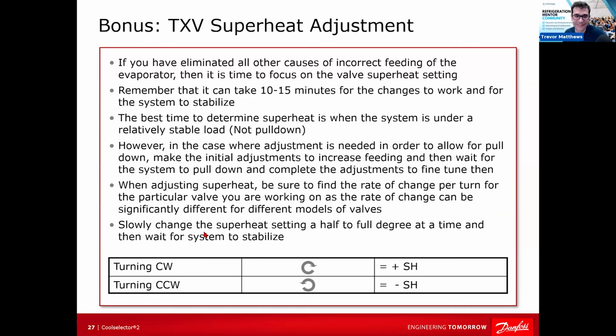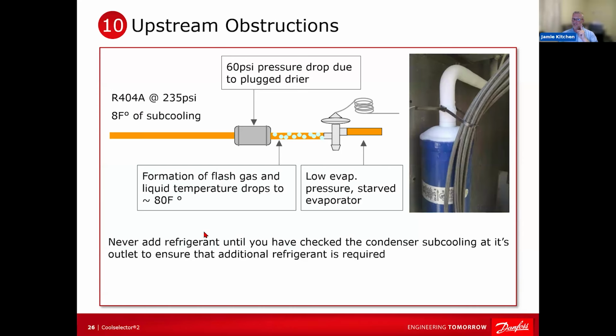Now keep in mind, the pressure drop through a filter dryer, get this, are you ready now, is determined by the connection size, not the volume size. So you can have a 16 cubic inch dryer, and if you put a certain capacity through it, you're going to have twice the pressure drop with a 3/8 inch connection as you will with a half. In other words, that 16 cubic inch dryer can have twice the flow through it with the same pressure drop with a 1/2 inch connection compared to 3/8. The size of the dryer determines the weight of refrigerant charge you can dry before it becomes saturated. So the pressure drop is determined by the connection size.